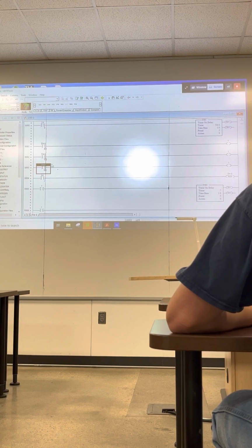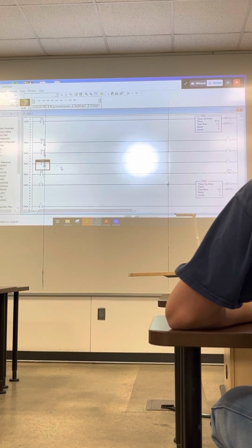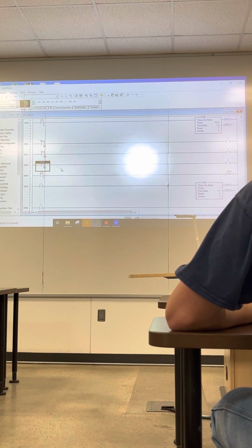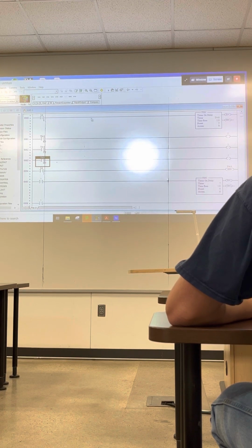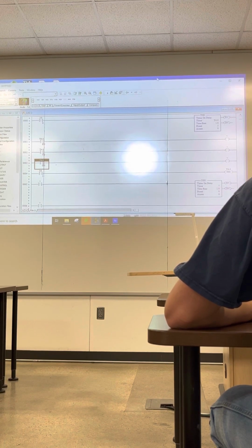Yeah, because that's what I had on my program. The done would unlatch the input that would control the timing, so it'd go off immediately. And in reality, there was probably so many microseconds when it was on, but it worked so fast that you'd never be able to see that, because it checks all these, then changes all these, then checks all these, changes all those. That's why in real fast processes, scan time or cycle time could play a role.